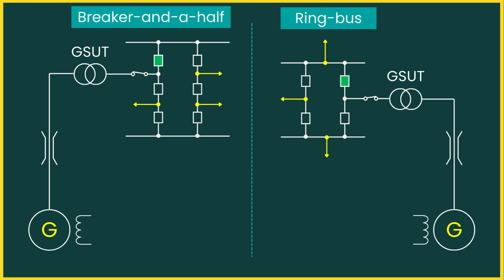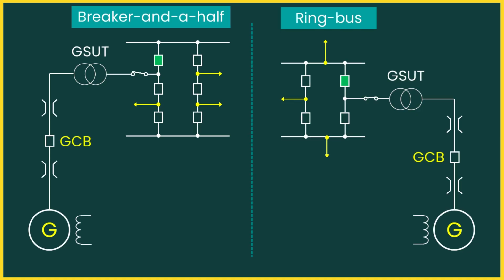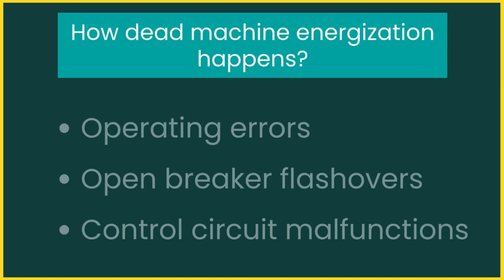In EHV breakers, high dielectric stress and small contact gaps can cause a flashover. Generators connected through low-voltage generator circuit breakers are also at risk. Accidental breaker closures, or flashovers due to loss of dielectric strength, have been reported in many plants. So, that is how inadvertent energization begins. Now, let's look at what actually takes place when dead machine energization occurs.